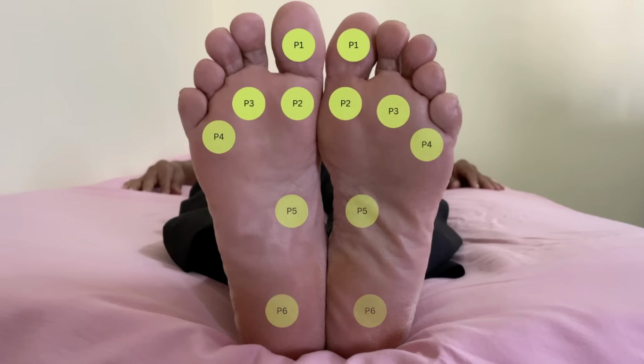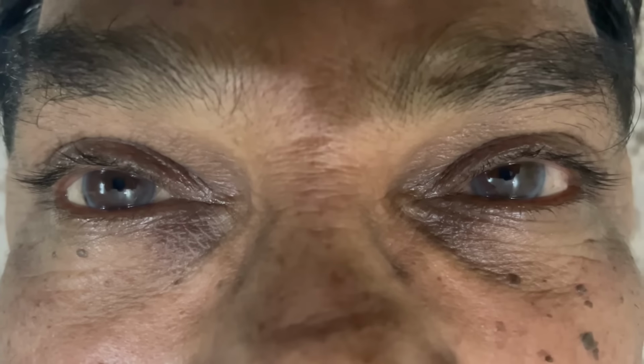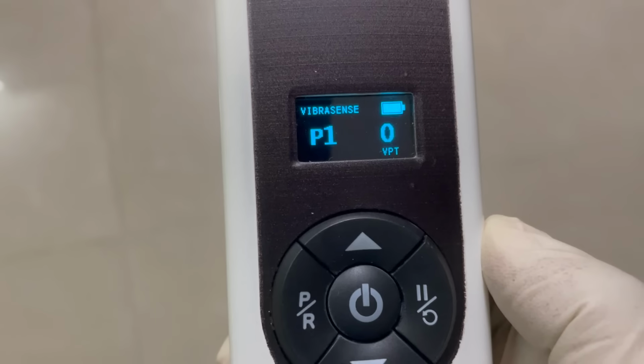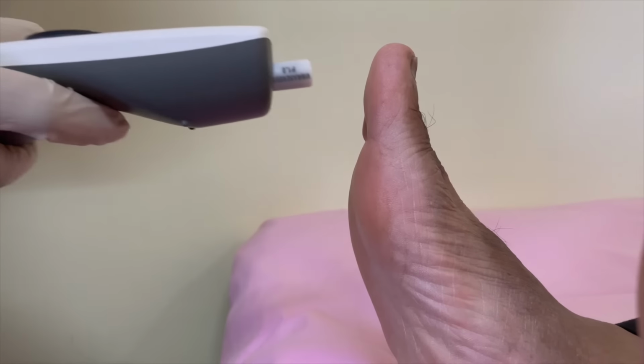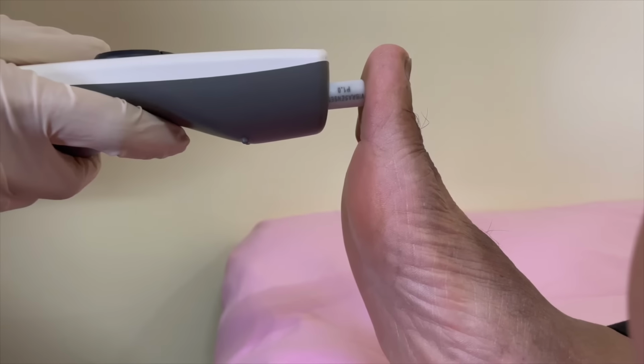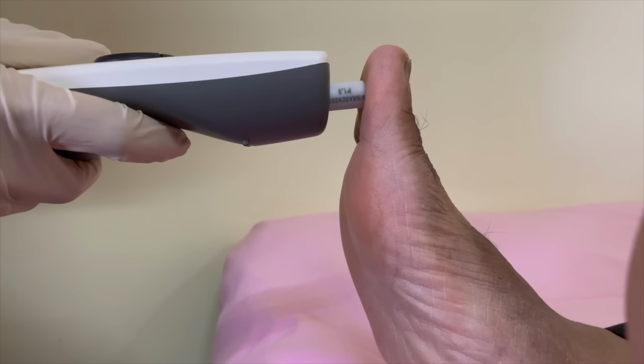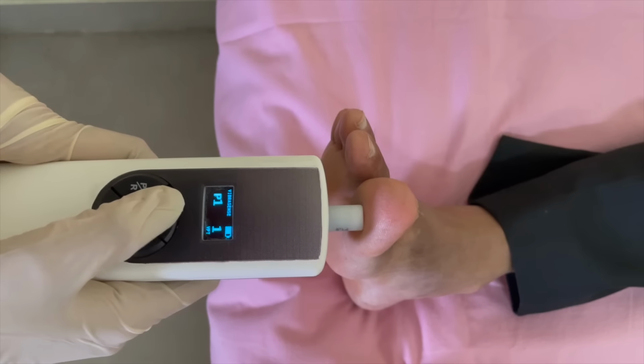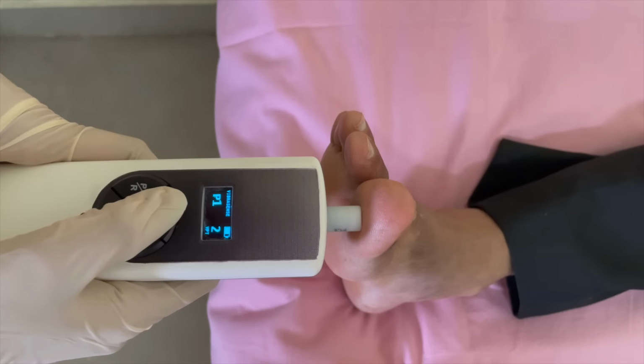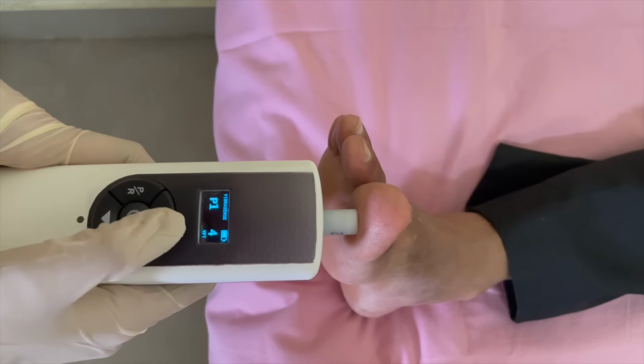These are the 6 points you will test on each foot. To avoid bias, you may ask the patient to keep their eyes closed during the test. Start the test with position at P1 and VPT at 0. Place the vibration probe on the testing point P1. Ensure that the probe is perpendicular to the skin surface and gently touching the skin. Slowly increase the amplitude using the up arrow until the subject feels the vibration sensation and affirms.